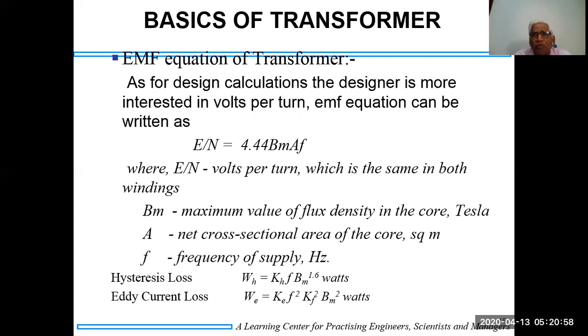The design of the transformer should match the frequency of the local authority. In India it is 50 cycles, in the USA it is around 60 cycles. All Commonwealth countries are using 50 cycles supply. Now, hysteresis losses are proportional to flux raised to the power of 1.6, whereas eddy current loss is proportional to flux raised to the square. So the equation is also important. You can say losses are proportional to frequency. Sometimes it is frequency squared. Losses are also proportional to the maximum flux value, Bm. So if the flux is more, the losses also will be more. So all the parameters, we should be very thorough about that, right?